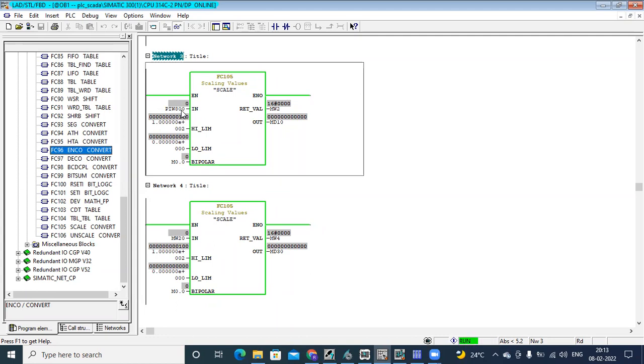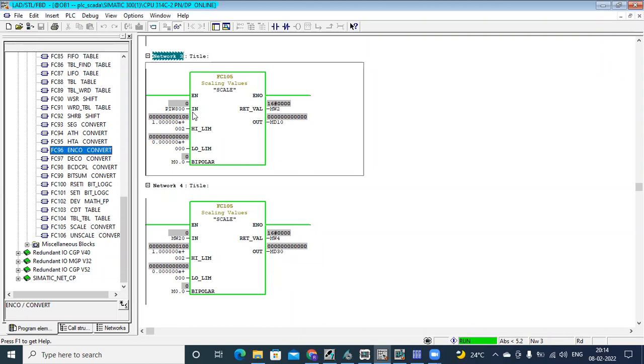The PLC cannot understand those units, so what we are doing is converting those units into our required electrical signal for the PLC. It is in a predefined range like 0 to 10 volts, minus 10 to plus 10 volts, or in current like 4 milliamps to 20 milliamps, or 0 to 20 milliamps. After conversion from non-electrical to electrical signal, we again need to convert that into our required count value.